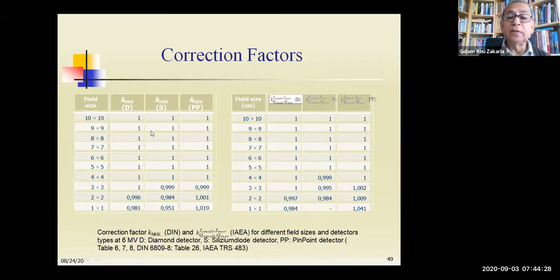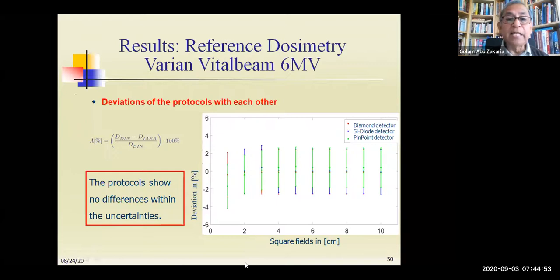So here we have taken for these 3 chambers, the diamond, diode, and pinpoint chamber, the correction factors from both protocols and put them here so that you can better understand the values for each protocol. Here are the values from the DIN protocol. Here it is more or less the same, and then we have determined, according to the procedures, the reference dosimetry for 6 MV. You see the values for both protocols, with uncertainty. The protocols show no difference within the uncertainties. Yes, both protocols give the same values for diamond, diode, and pinpoint chamber. And we have drawn it here.